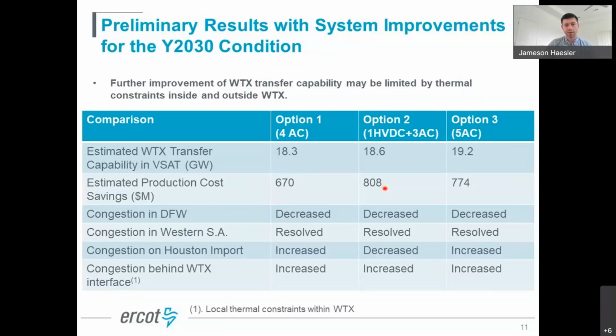However, if you look more closely at option 2 versus option 3, you do see an increase in West Texas transfer capability in option 3, but you do not see the same production cost savings seen in option 2, which has that HVDC line going straight into Houston. So these results underscore the necessity, when looking at the interface, of keeping in mind the influence of those downstream as well as upstream thermal constraints.